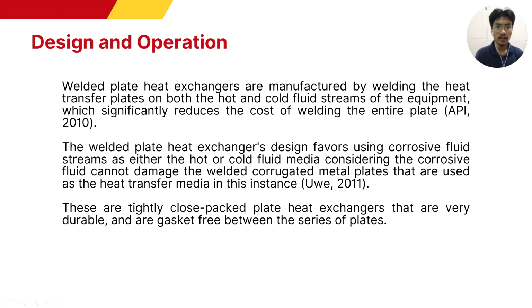Next, the welded plate heat exchanger's design favors using corrosive fluid streams as either the hot or cold fluid media, considering the corrosive fluid cannot damage the welded corrugated metal plates that are used as the heat transfer media in this instance, based on UWE 2011. So the plates on a welded plate heat exchanger are basically made up of strong metals against almost any type of fluid, and are also highly resistant to corrosion or rusting.